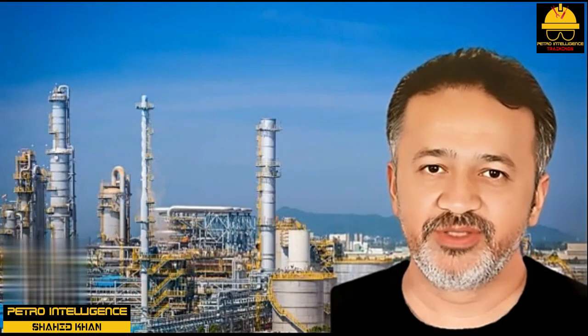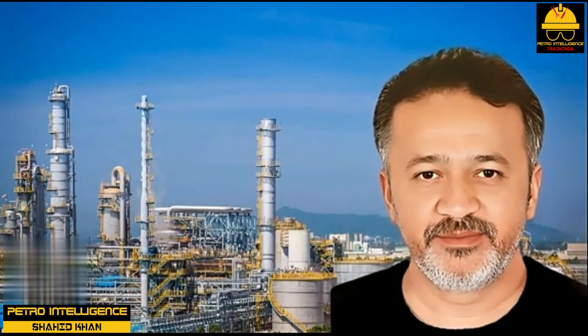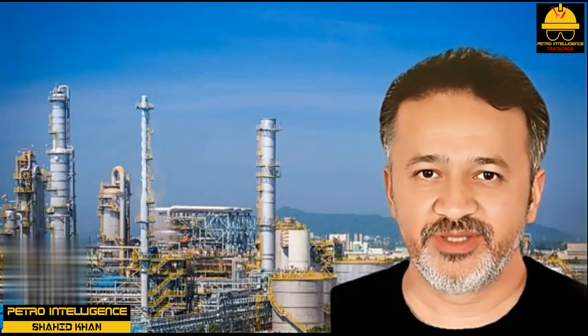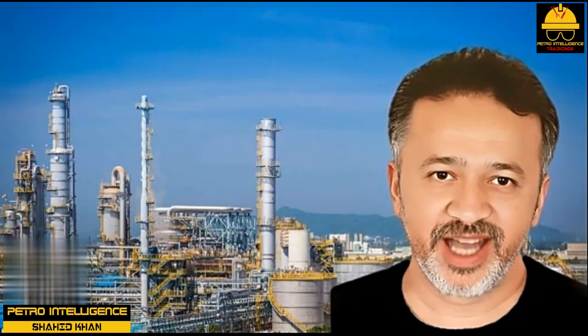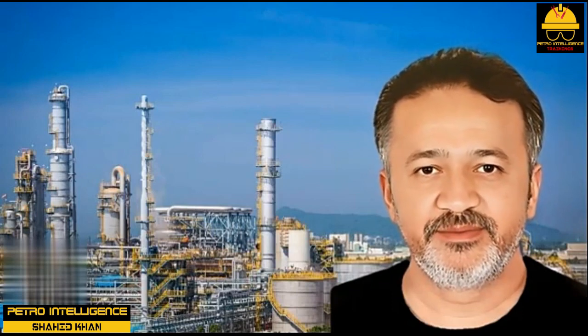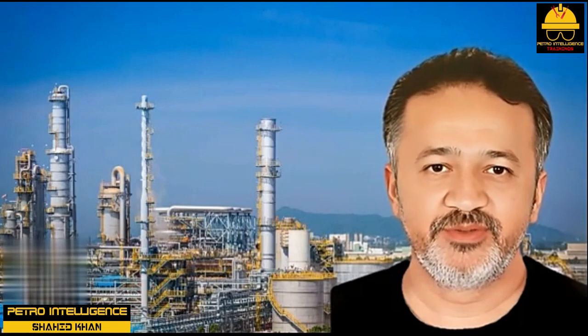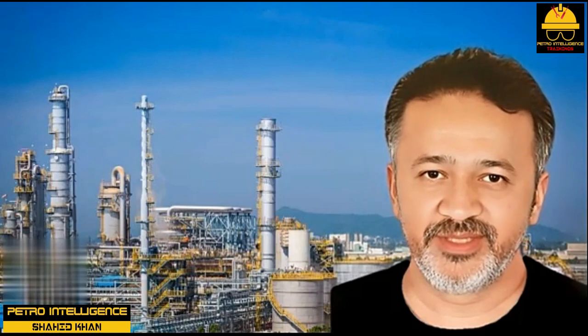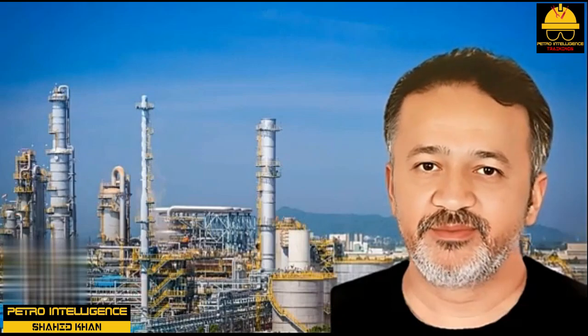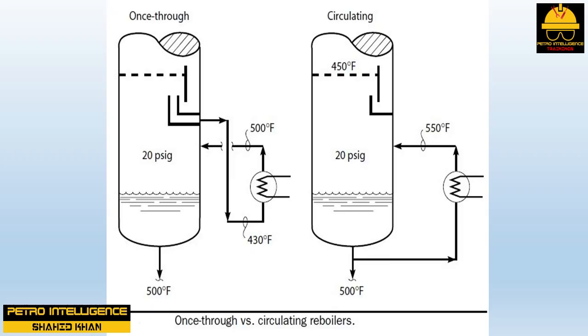Returning the effluent from a once-through reboiler with a vertical baffle to the cold side of the tower's bottom would make it work more like a circulating reboiler — which is worse. The once-through reboiler functions as the bottom theoretical separation stage of the tower. The circulating reboiler does not, because a portion of its effluent back-mixes to its feed inlet. This back-mixing ruins the separation that can otherwise be achieved. Regardless of reboiler type, the tower bottom product temperature must be the same to meet product specifications.